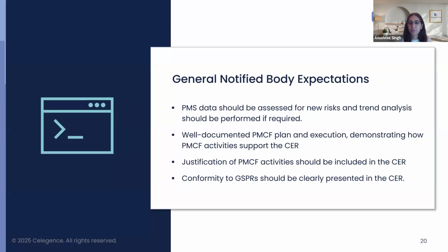And coming to PMCF, post-market clinical follow-up, it is a proactive process that is designed to continuously gather clinical data on the safety and performance of a device once it is on the market. A well-documented PMCF plan and its execution are essential components of the clinical evidence framework. The CER must clearly demonstrate how PMCF activities align with and support the conclusions of the CER. What are the specific clinical questions or residual risks that the PMCF is addressing? And what data collection methods are being used? For instance, these could be either registries, surveys, or observational studies.